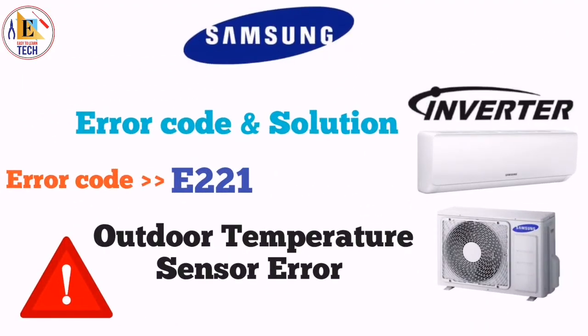When you see an error on your indoor display LED light, when LED 1 and LED 3 are blinking, it means there is a fault in our outdoor unit. When you go near the outdoor unit, you will see error E221. It means outdoor temperature sensor error. At that time, first of all, you have to check all the connections of your sensor, put it in the correct position and connect it properly, and again check if the error has gone or not.